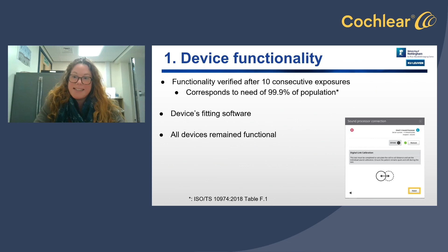So for device functionality, the device was exposed to the scanner's ISO center 10 times, which was deemed to cover the needs of around 99.9% of the population. All devices were found to remain functional once plugged back into the Cochlear software.